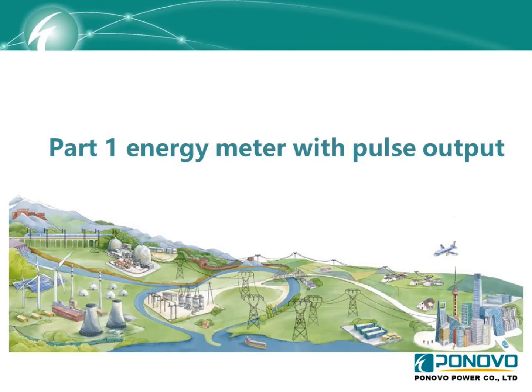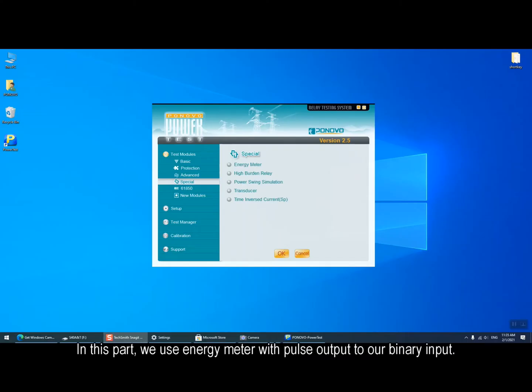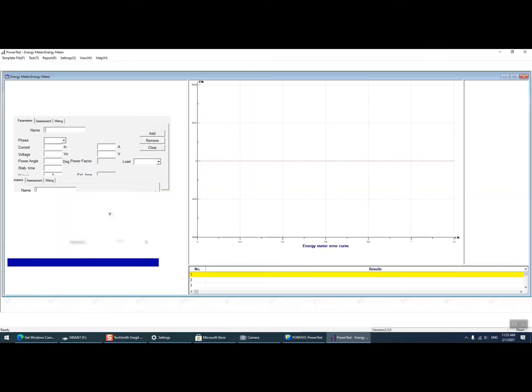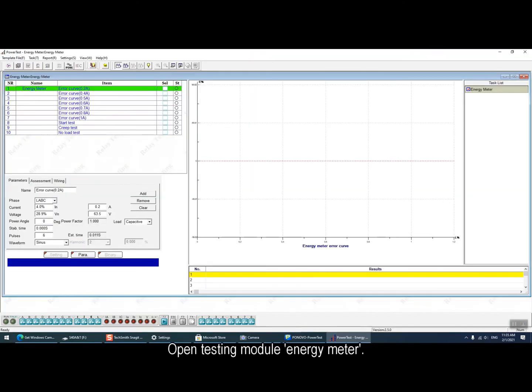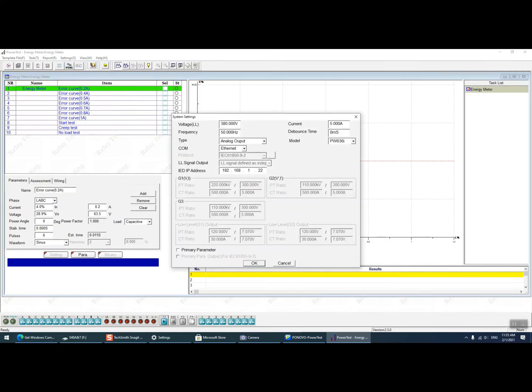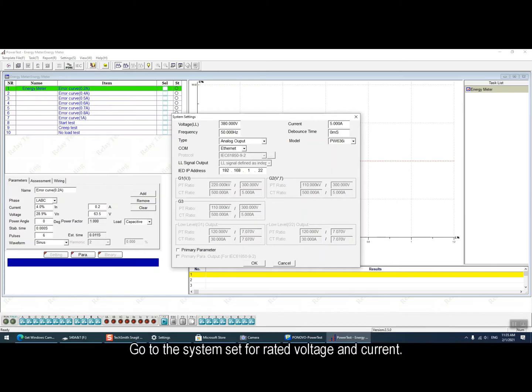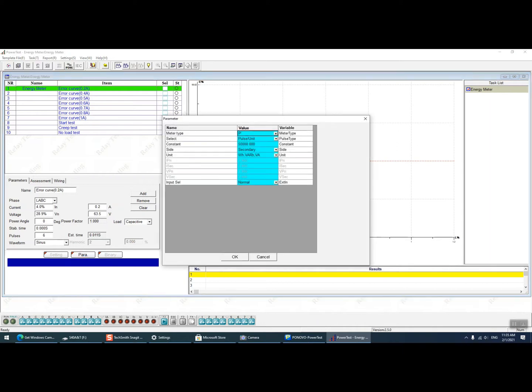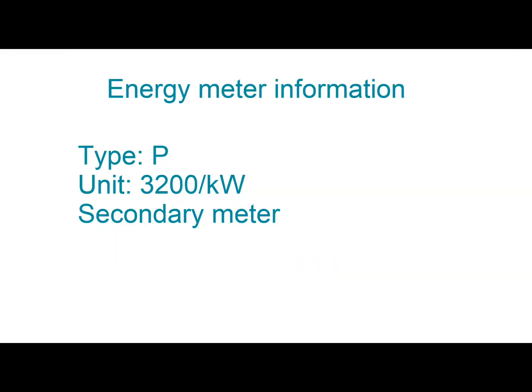In part 1 we will show how to test the energy meter with pulse output. For this kind of energy meter, we normally connect the energy meter with pulse output to our binary input. Firstly we open the testing module energy meter. Go to the system set for rated voltage and current setting. Here we can do the setting according to energy meter parameters such as the type, unit and secondary meter.